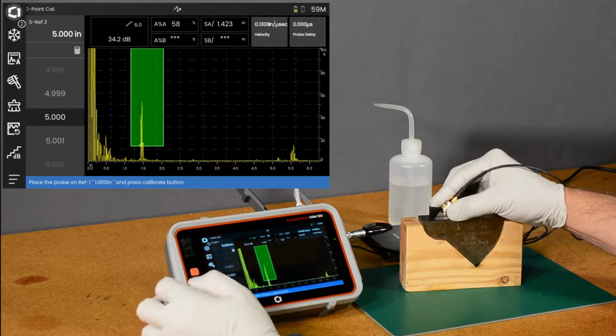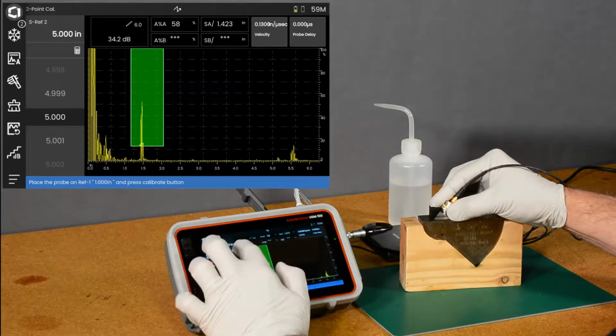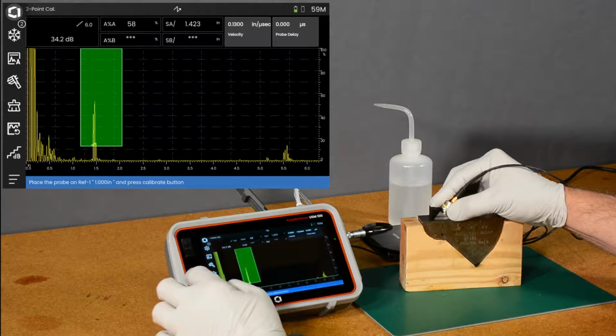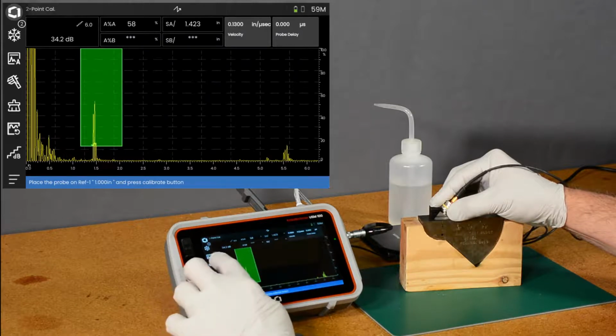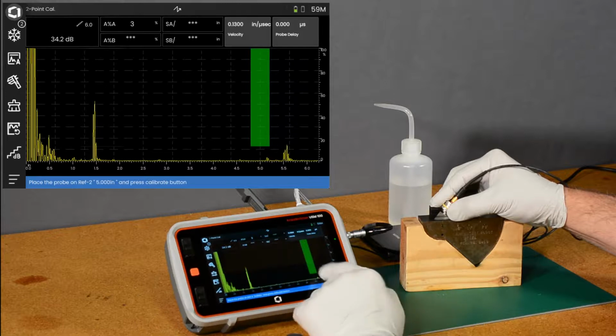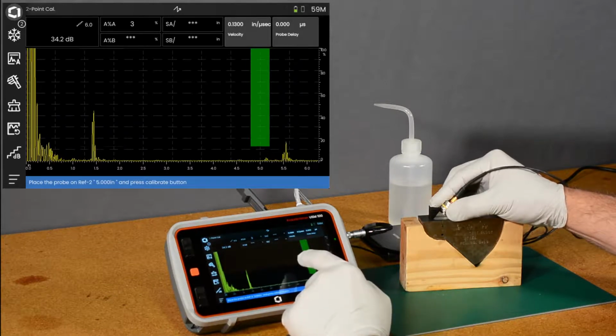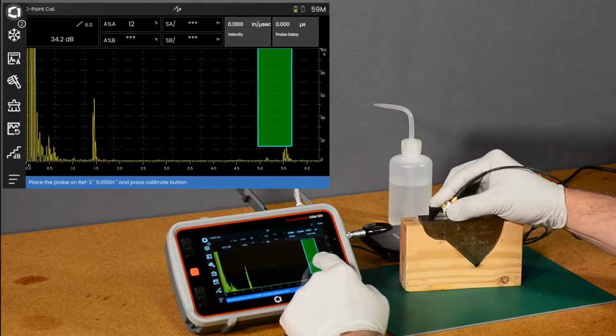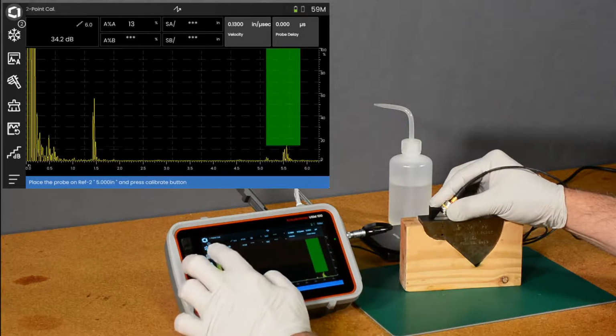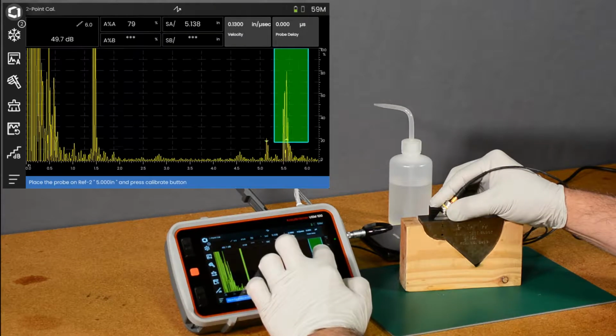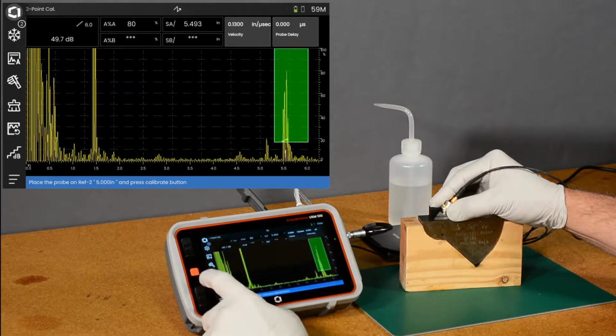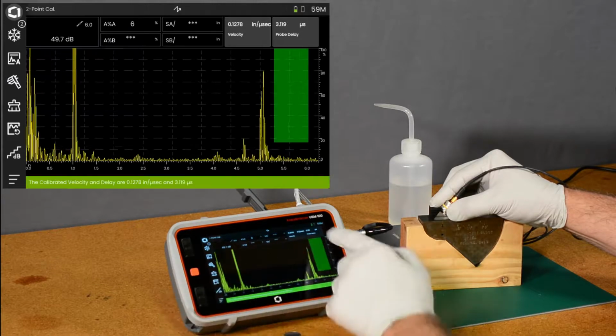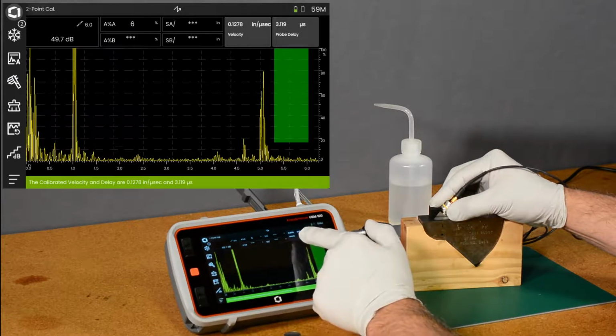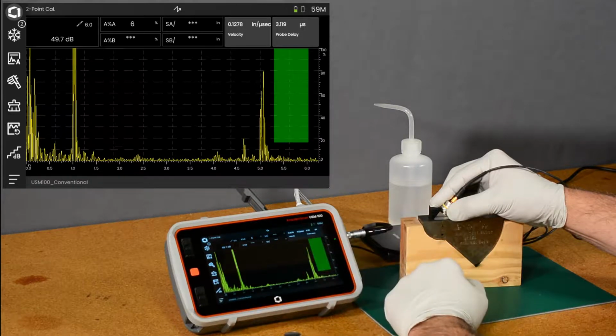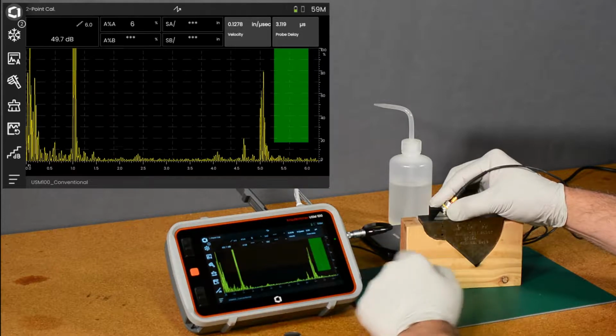All right. So now we can go ahead and do our calibration. Let's close that. Close that. Let's hit our cal button. And it says show me the 5-inch echo. So let's come out here. Get some more amplitude. Gate over the 5-inch right there. And hit cal. And it calculates the velocity at 0.1278 inches per microsecond, and our probe delay at 3.119 microseconds.